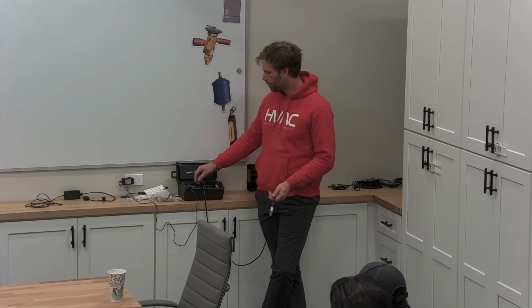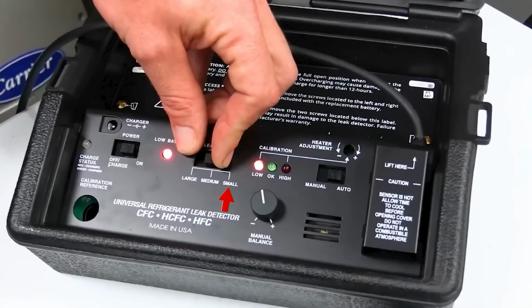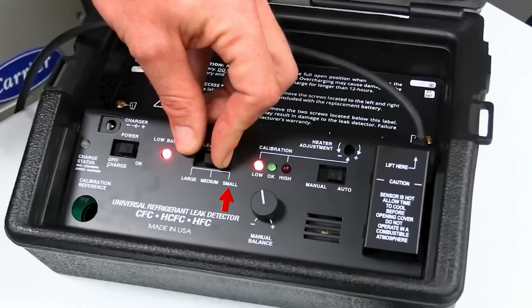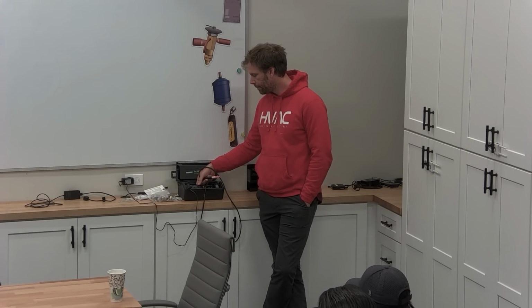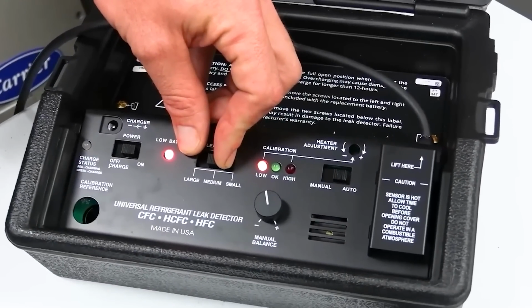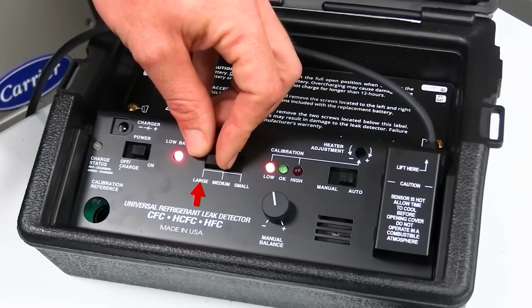Okay, medium and large. When it's on small and you have a large leak, you have the potential to pull in a lot more refrigerant and put a lot more wear on your sensor than on large or medium. And also it can be very hard to pinpoint a large leak. So if you open up your evaporator panel and you're looking around for a leak and it's going off all over the place, move it all the way to large, and then you can get closer to the leak. It might be right there on the line next to the evaporator coil.